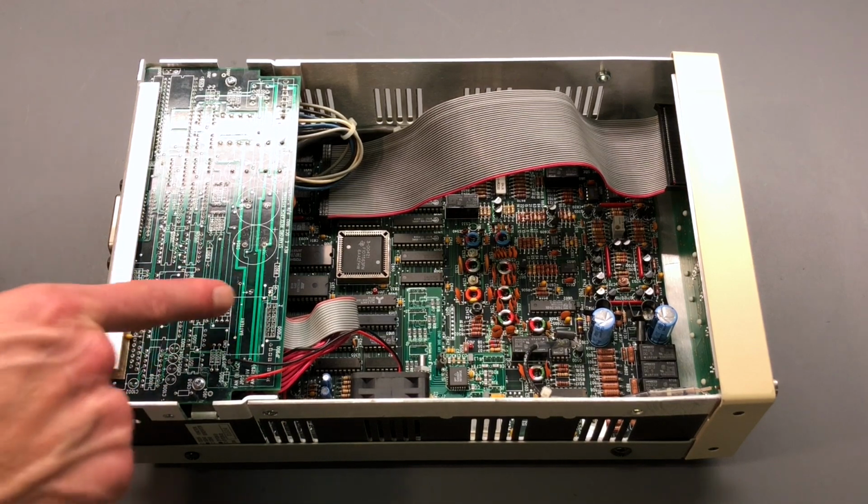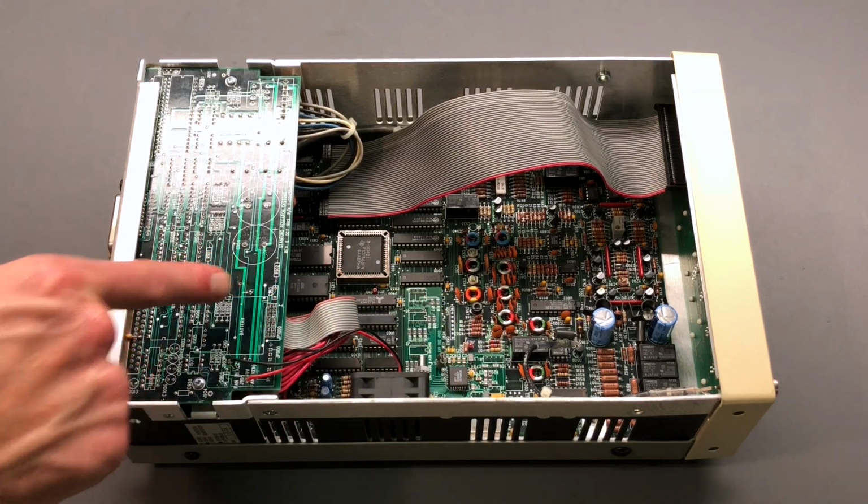So it makes sense that that cal byte may need to be adjusted. Now here's the thing and how it operates. The ROM cannot be changed, all right? However, when the instrument is powered up, all of the data for these cal bytes that is held in ROM is moved over to RAM, or random access memory, and that RAM is battery backed. And we do in fact see a battery right here. Okay, this is of course the back side of the circuit board. The other side is where the battery is down here, and it's soldered there and over here.